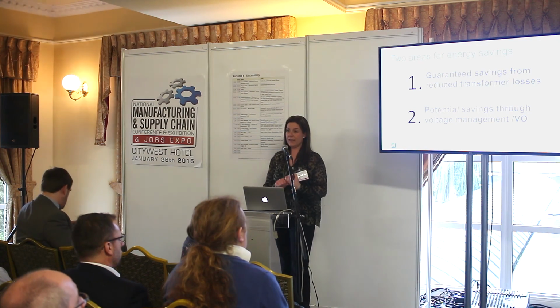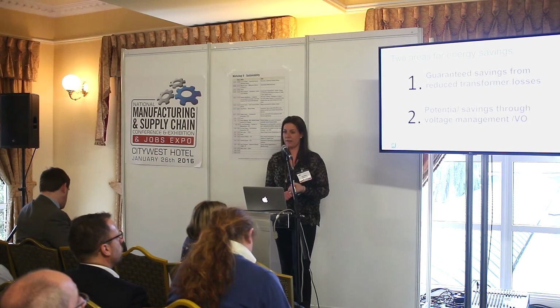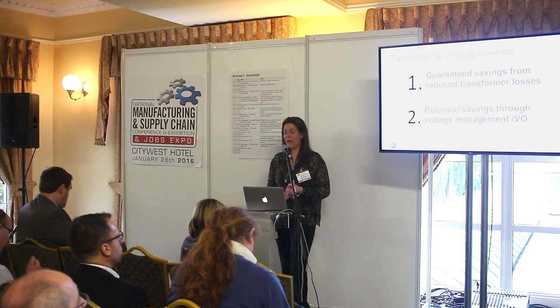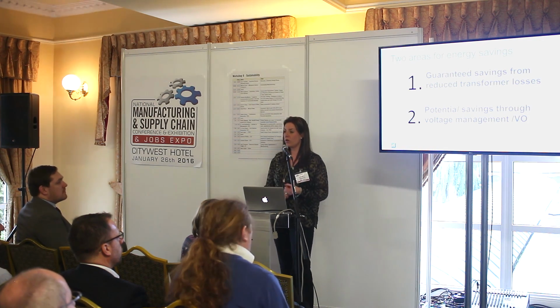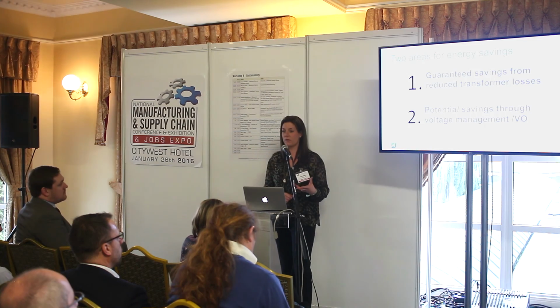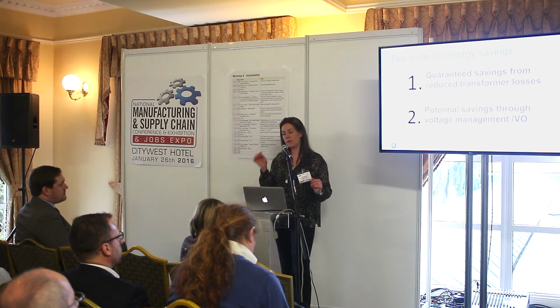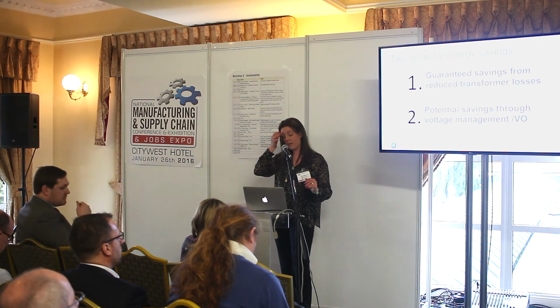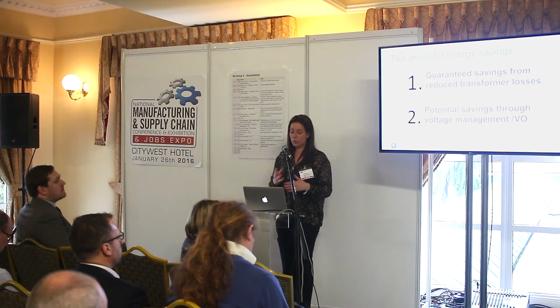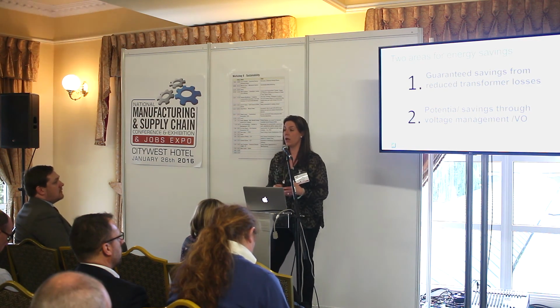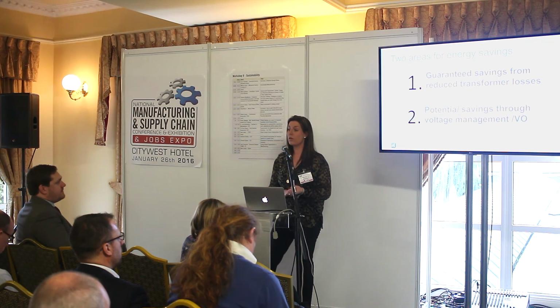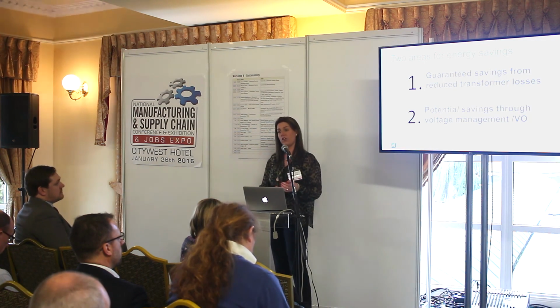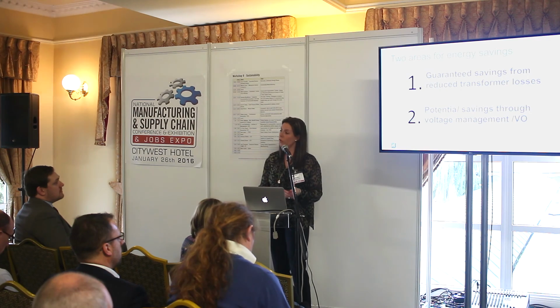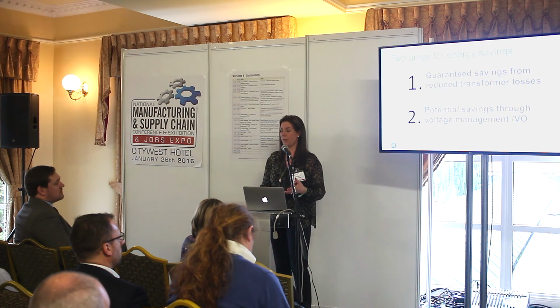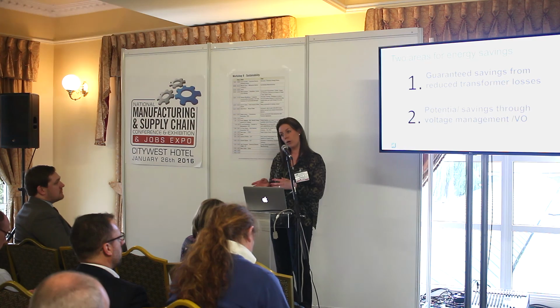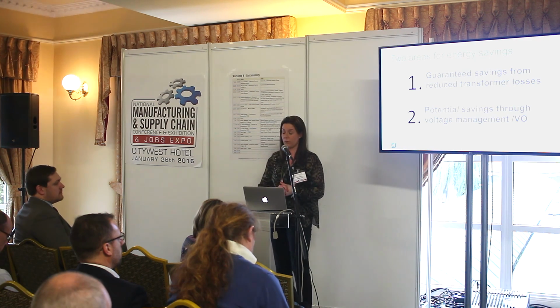So you've got your guaranteed loss savings there. This is a guaranteed value, but also, if anybody's heard of or experienced voltage optimisation or voltage management, some people recoil with that word because it's got particularly bad press on the low voltage products. But if you do have a site survey and you realise that some of your load types would benefit from reducing voltage to them, you could use the transformer for that purpose, because it has a tap changer on it.